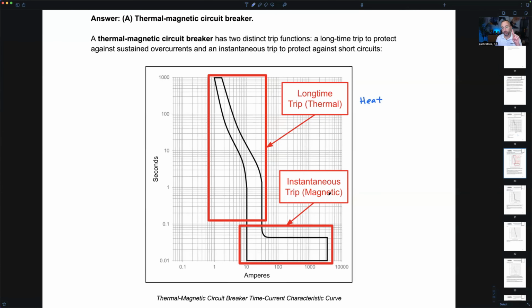What region is this down here? That big fat horizontal rectangle that sits right on our horizontal axis, or sometimes, if you can adjust it, there might be a little gap here, but for the most part it's going to be pretty close. That's always our what? Yeah, that's always our instantaneous trip region. Instantaneous trip is for what? Instantaneous trip is for high fault current.